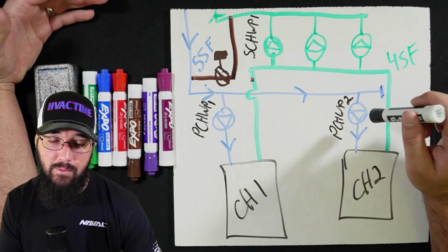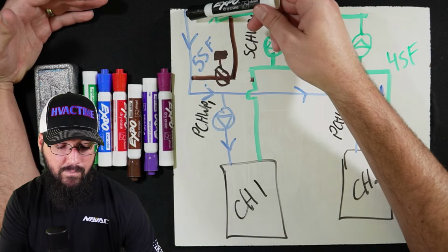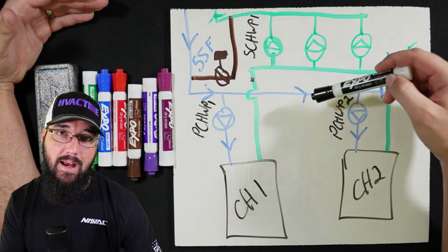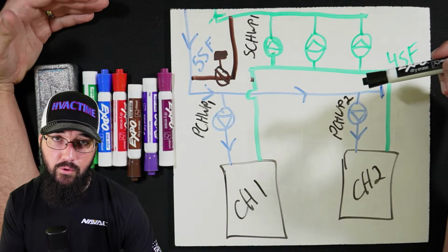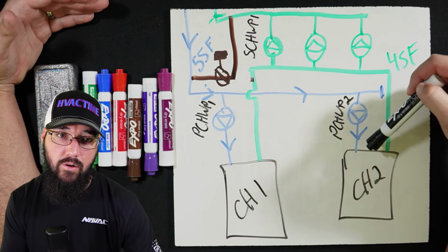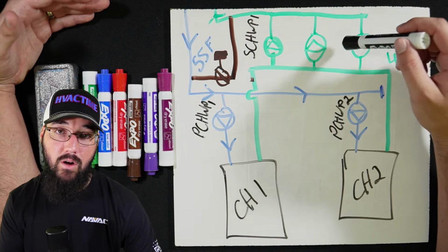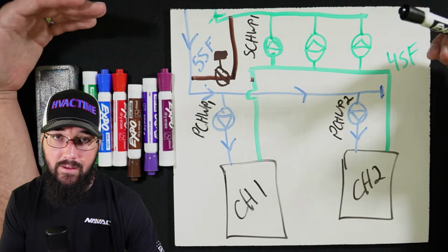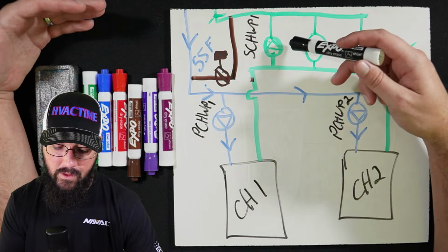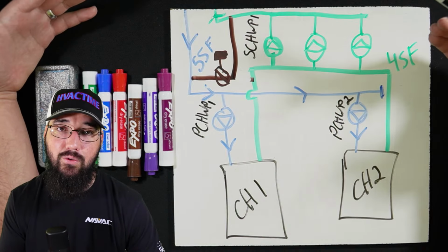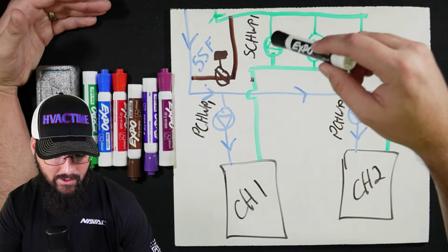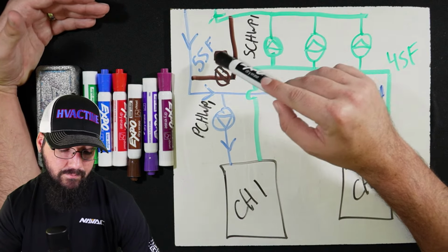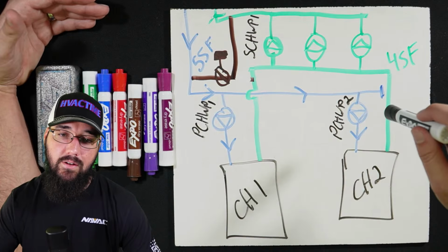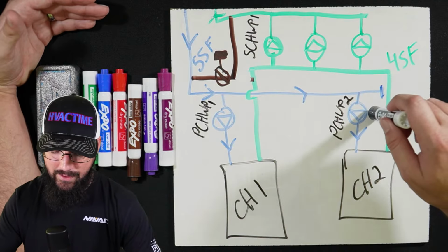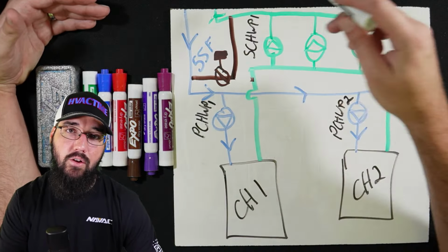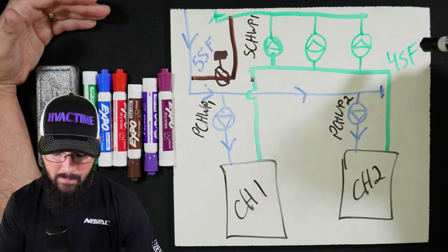We need a set GPM, because if we don't have this bypass, these primary pumps will start really pulling down on the return loop trying to feed the chiller, and then we start choking the chiller of water because we're not running enough secondary pumps. We don't need to, or we can't, because we don't have the load to load up that many secondaries, or to get the secondaries to flow that many GPM at the time. So we can use this bypass to recirculate that loop water so that we can maintain GPM at the chiller, even though we've got less load at our air handlers, let's say.